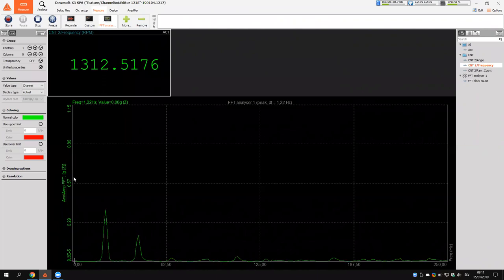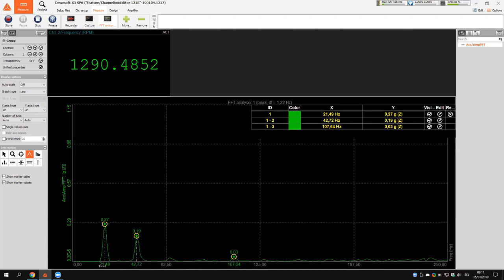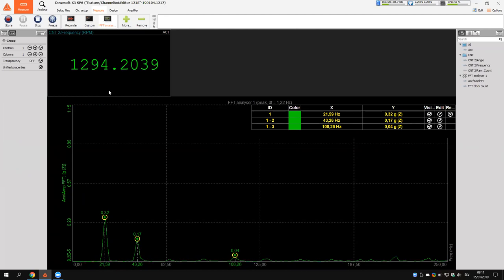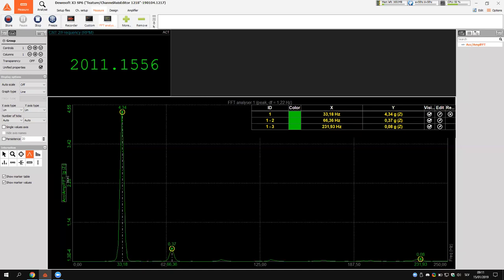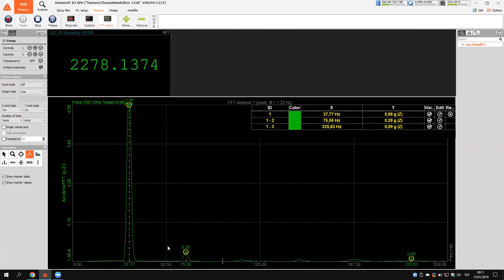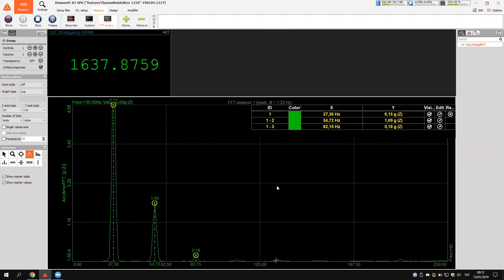My machine is running at 1300 RPM. Adding a couple of markers, I can see that the first harmonic is the highest one at 21 Hz, which is consistent with the measured RPMs. Now let's see what happens when I increase the RPMs — the frequency spectrum changes, the first harmonic slides in the frequency domain, and different harmonics appear or disappear during the run-up. That is the basic idea of order tracking: to track the frequency spectrum in relationship with the RPM.